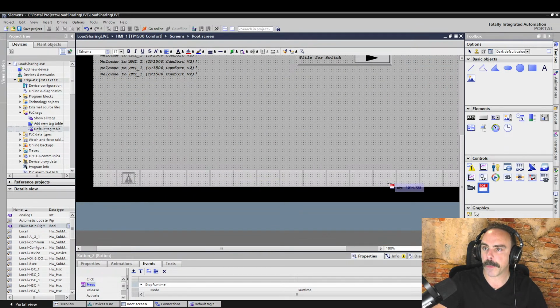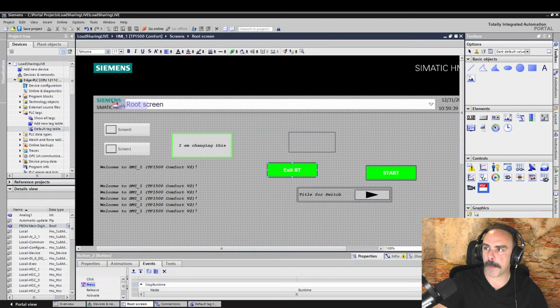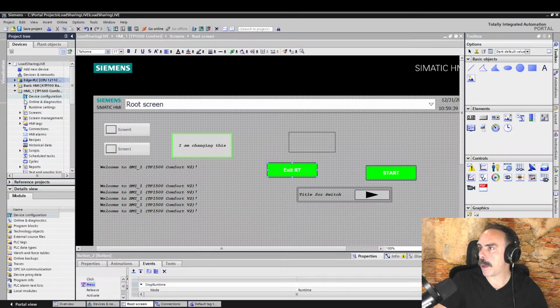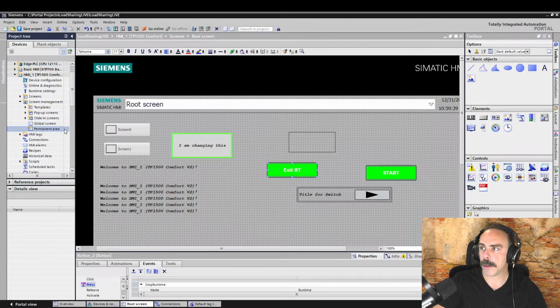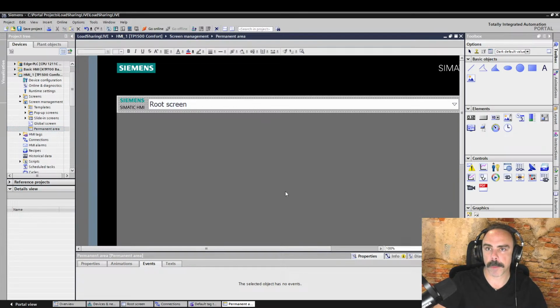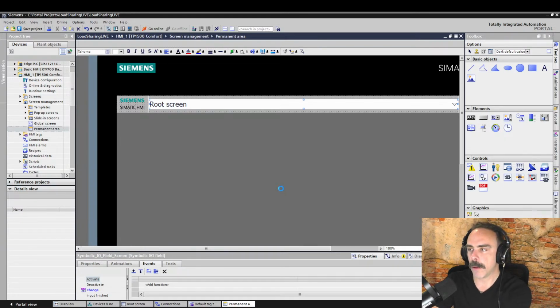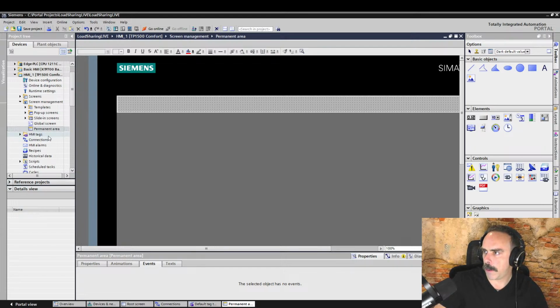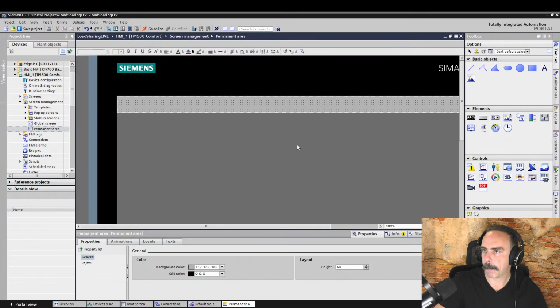So this down at the bottom is the template. This up at the top is what is called a permanent area. So what we're gonna do - that's not our HMI, this is our HMI - we're gonna go to screen management. The first thing we're gonna look at is the permanent area, because this is the guy up here at the top. If we don't want a permanent area, we can just Control A, delete everything, and then - I want to say there's a way to say use permanent area, but worst case, you can set it to 0.